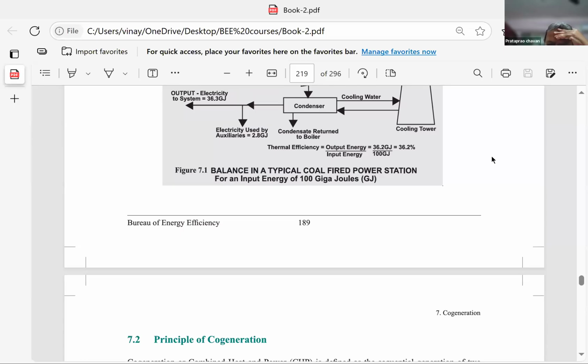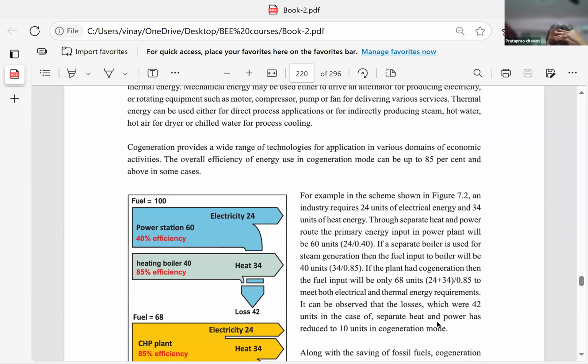Now, if we change this picture by using the heat for other purposes in the factory. Look here, the fuel has given you 100 units of heat. From this 100 units of heat, I am generating 24 units of electricity. I am dividing this between power generation, 60% of the heat, and heating for other purposes, 40%. If I use it only for electricity generation, the blue diagram here, only 24% is used in electricity, and the remaining goes to loss, 42%, which is going to the atmosphere.